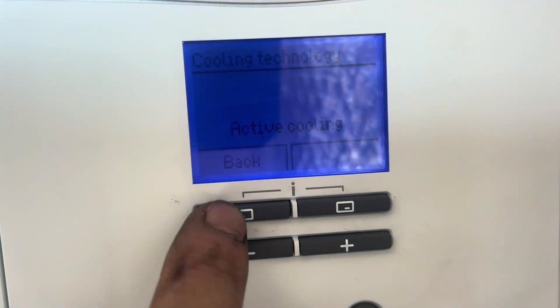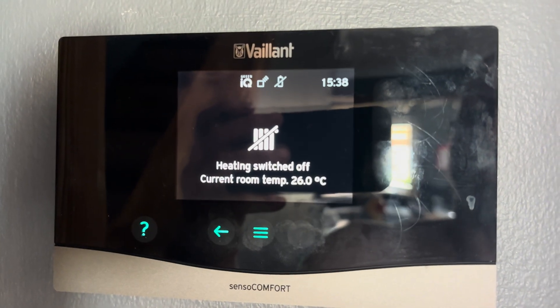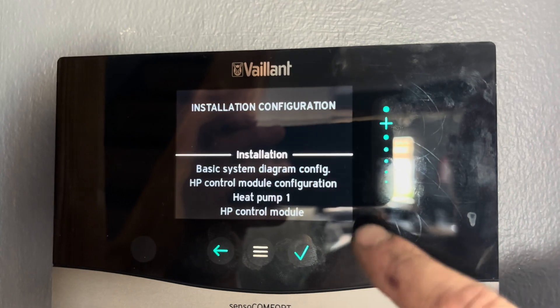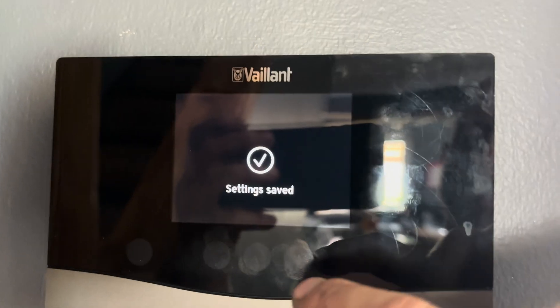Exit back out by pressing this button. Now we need to set up the sensoCOMFORT controller. Press the menu buttons down to settings, then installer level, then installation configuration, and go into installation. Enable automatic cooling activated.